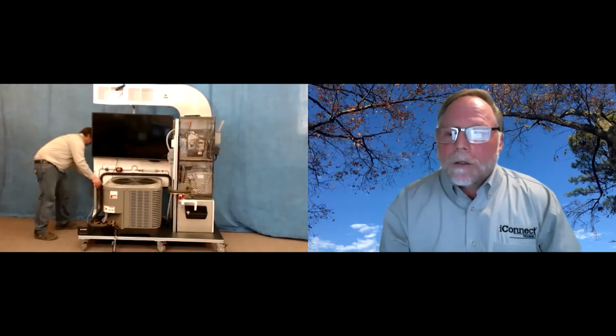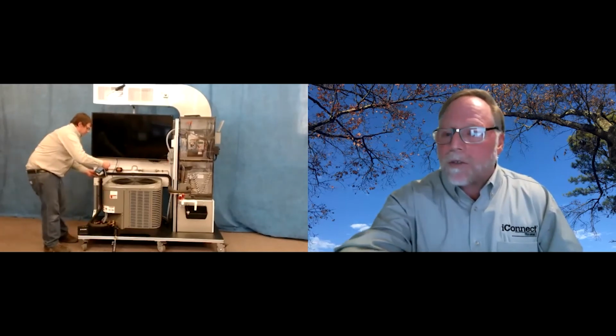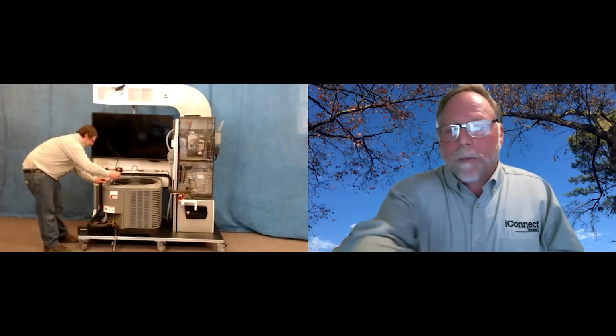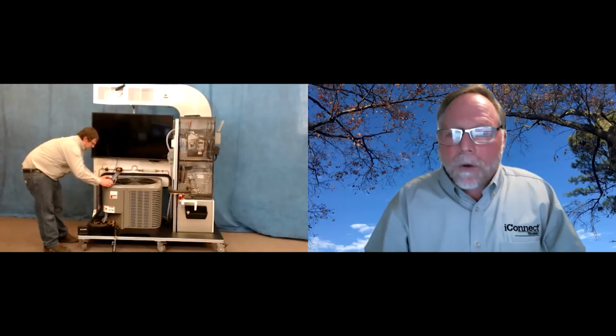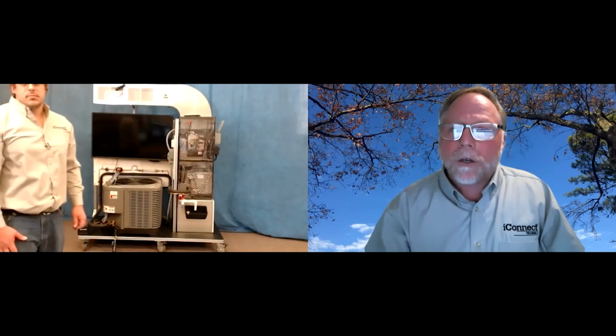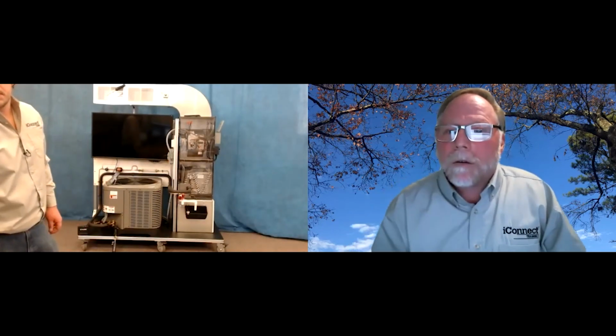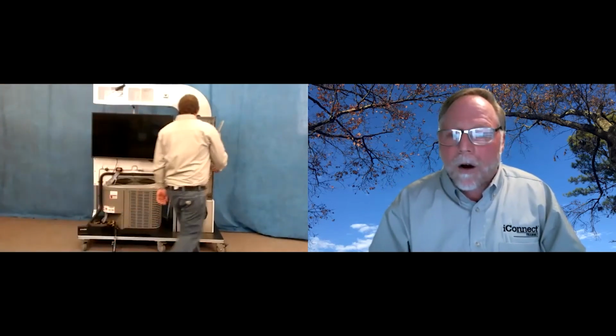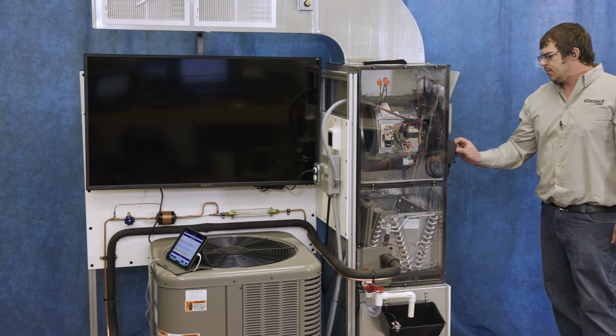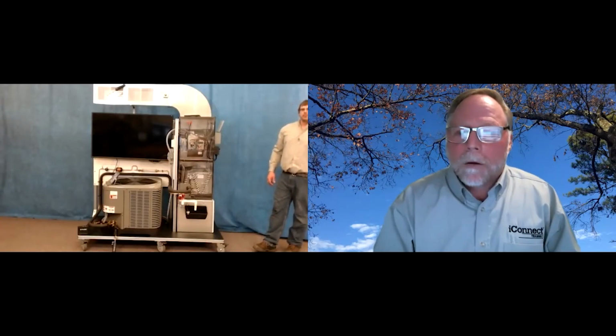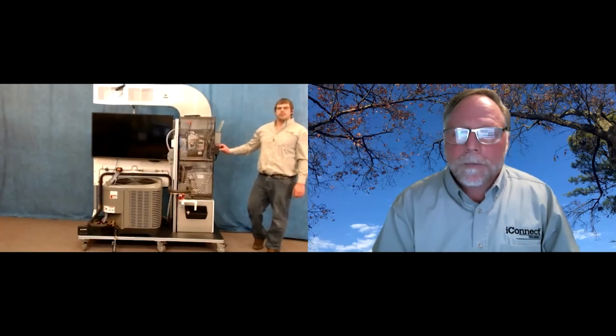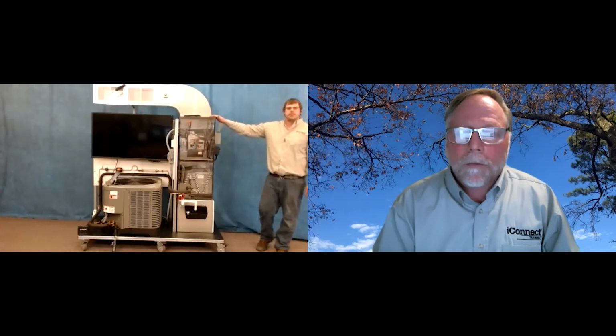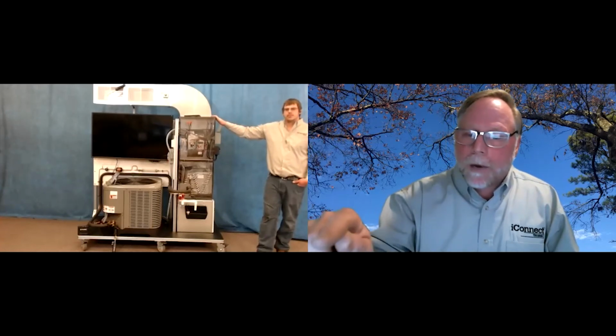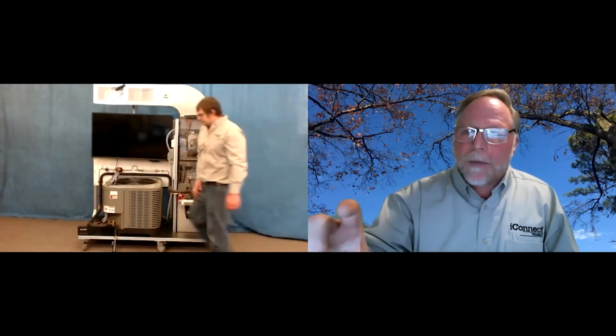Okay, now there we go. So you can immediately see we've got a return air dry bulb of 71 degrees. Our relative humidity is 28%, and our wet bulb is 53. And then if you go down, Nick, if you got both return and supply there, go ahead and lower that fan speed again. And we can keep our eye on the temperatures and watch how they change. Now watch real carefully the supply air temperature. See, our relative humidity is starting to change, our supply air, our wet bulb starts to change. All that is affected by how much air we're moving across that coil.